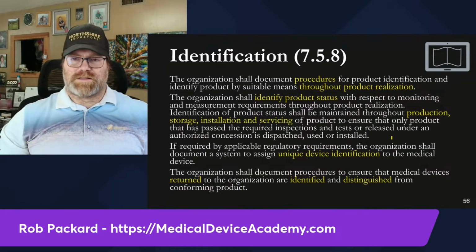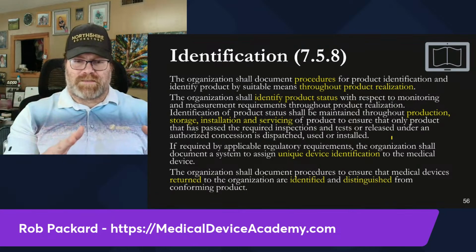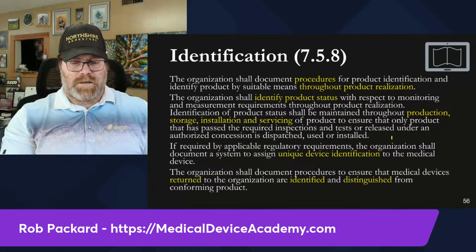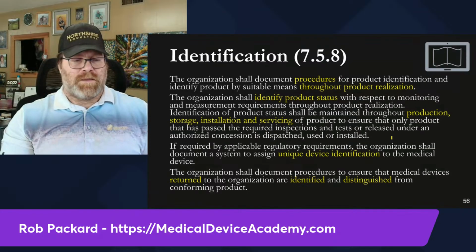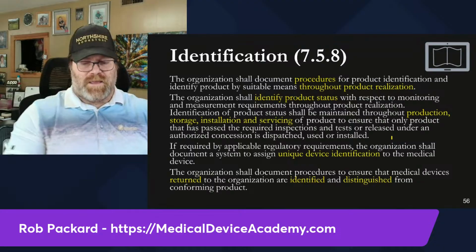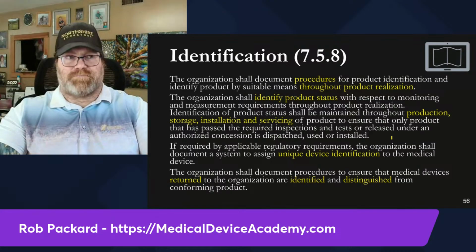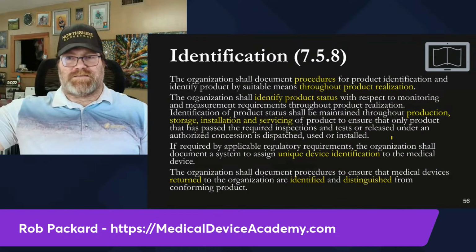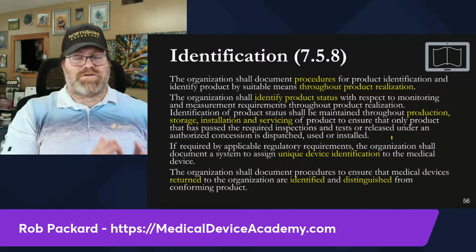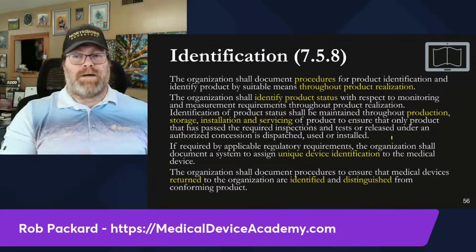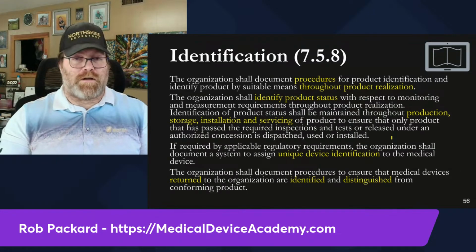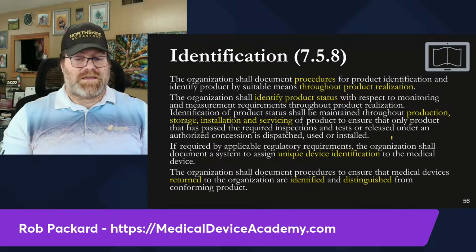The example that I always like to use is we're inspecting these implants and we open them all up and then we get them mixed up with paperwork because we have them all open at the same time. You need it very clear. These implants have yet to be inspected. This implant right here is being inspected. Those implants passed inspection, and the ones on the floor in the red bin failed inspection. So clearly designated by color, by physical location in my environment, and I've probably got it labeled somewhere on my desk, if I'm a QC inspector.